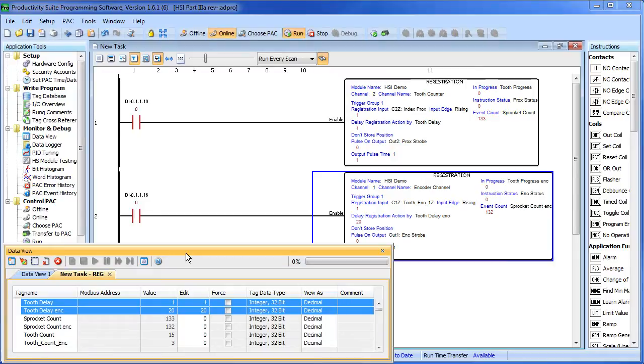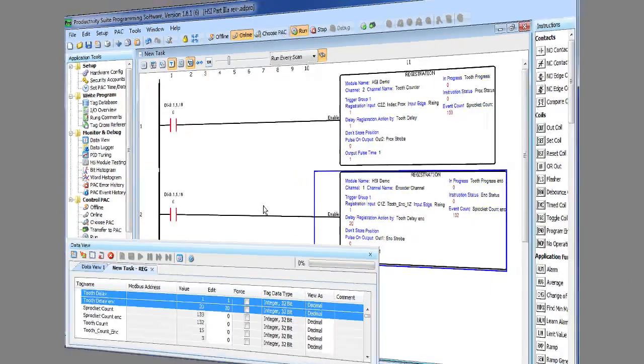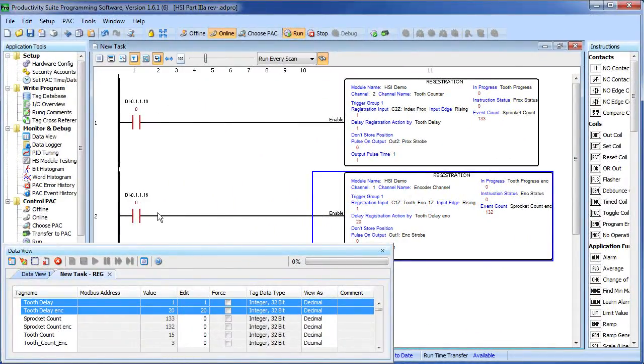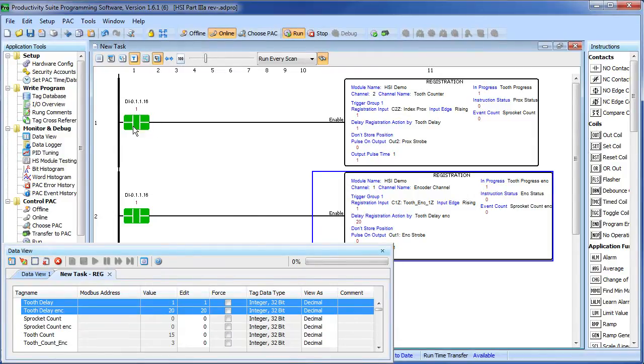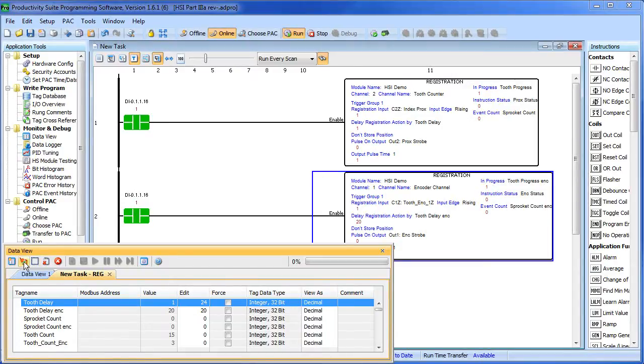Down here I've created a data view so we can keep an eye on some of those tags. We've made a bunch of changes. Let's go ahead and download that to the controller. We're ready to go. I'm going to reach down to the controller and enable both of these instructions by flipping the switch on the input simulator. Note that I changed the options to give me a block cursor instead of the lines. Both instructions are showing me that they're ready to go. Let me go ahead and push the proximity sensor delay back out to 24 like we had before, and we'll leave the encoder delay at 20.